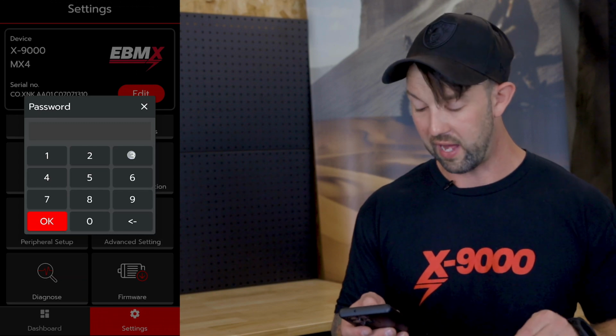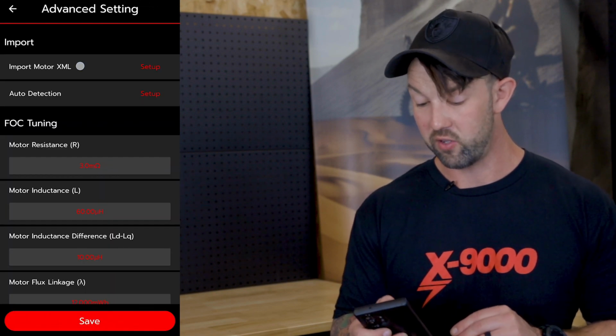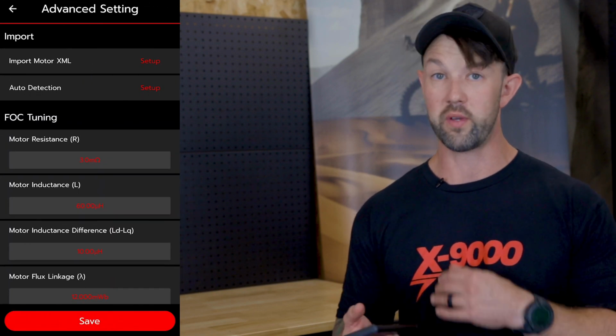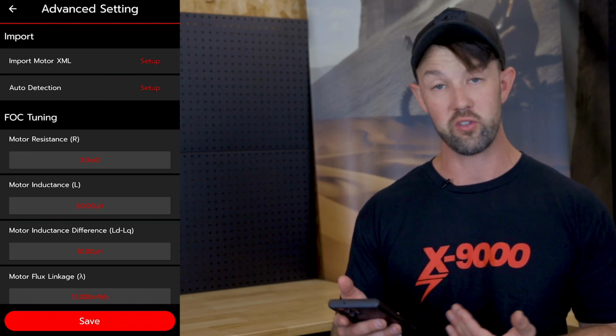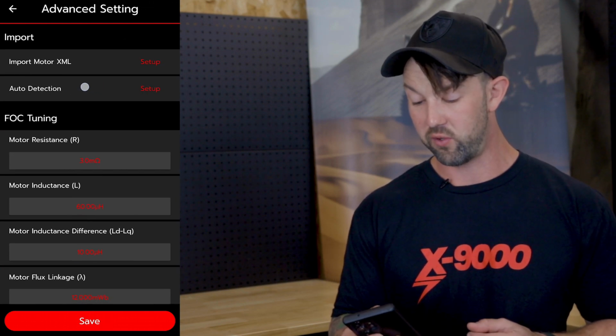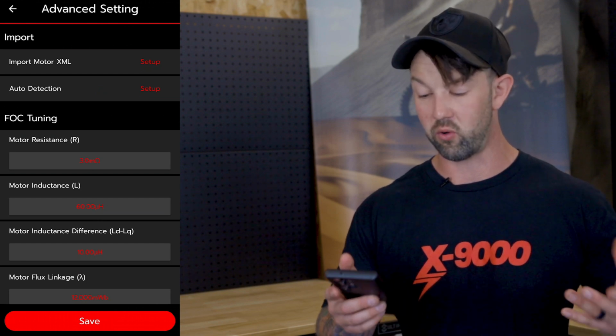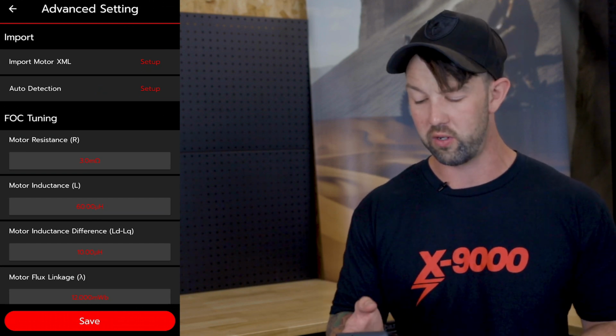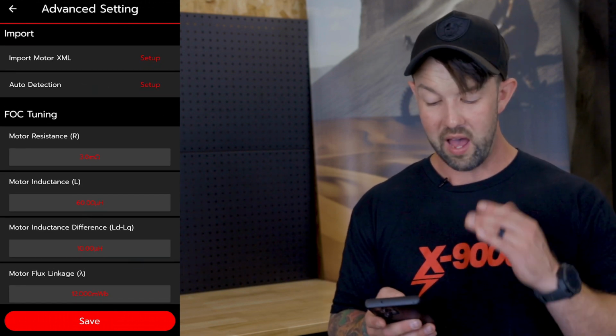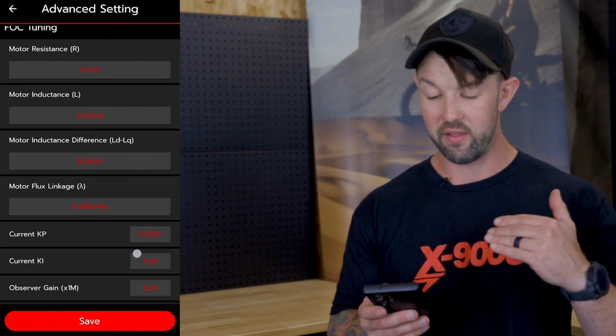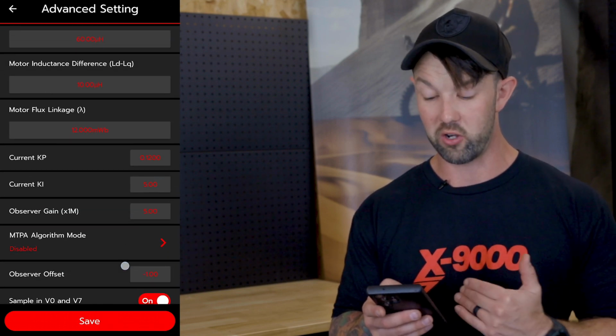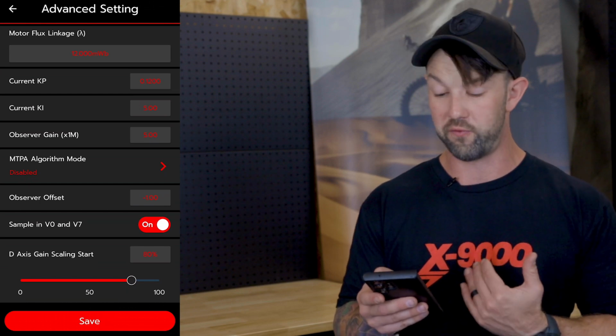Coming into advanced settings, you'll always need the code for this, and we'll give this out. In the advanced settings, you can import a custom motor XML. So if we've written a tune that isn't available in the app, you could load it here. Same if you have a custom motor and need to do an auto detection, basically an auto tune - this is where you would start. We have essentially everything you'd need to get a motor going and tuned correctly. This is what we use now in the field to tune.